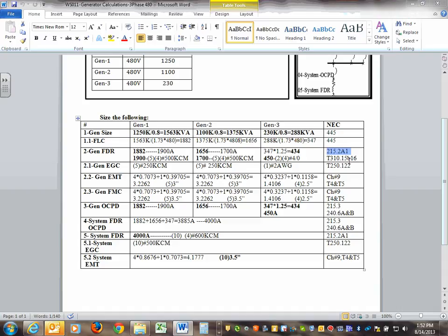It says, if the cables are tied to a 100% rated circuit breaker assembly, as in a draw-out switchgear, look at the condition, the exception. If they're tied to a 100% rated assembly, circuit breaker inside an assembly rated for it, you can size your circuit breaker and your feeders to the full load amps, no 1.25 is needed. This rule, I use it all the time when we have draw-out switchgear. Easy, because it's a 100% rated assembly, meaning if you have a 4,000 amp, theoretically, the manufacturer is telling us you can pull 4,000 amps out of it continuously for more than 4 hours.